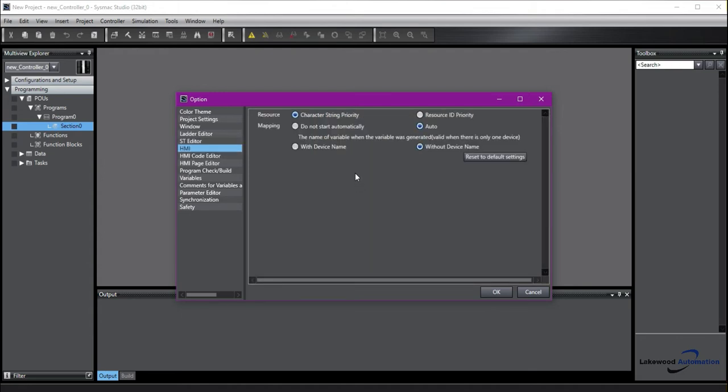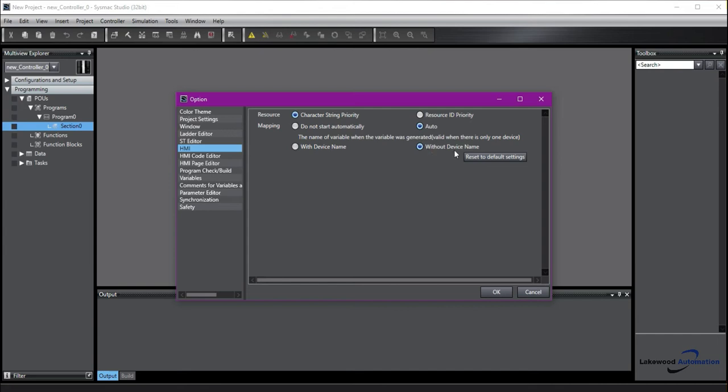HMI is going to let you make some changes that will make it easier to program an Omron HMI. So we want to make sure that we have this mapping changed to auto. This means that it's automatically going to map the variables from the CPU to the HMI. And we want to do it without device name. This just keeps the variable shorter, because when we do it with the device name, we have the device name underscore the variable, and it can be very long and tedious to work with.